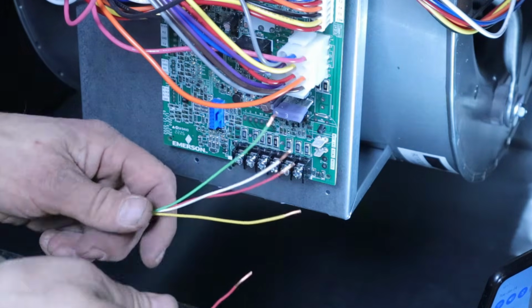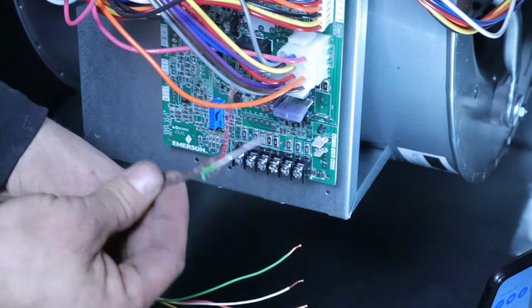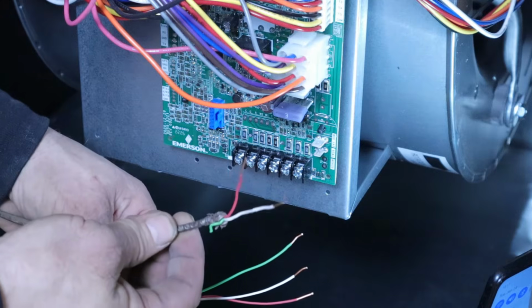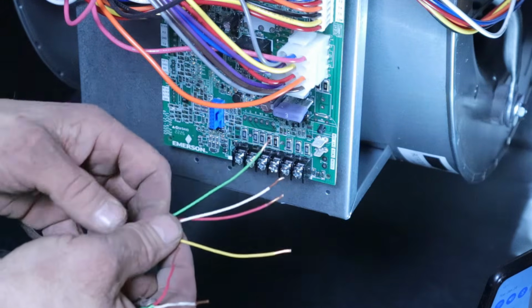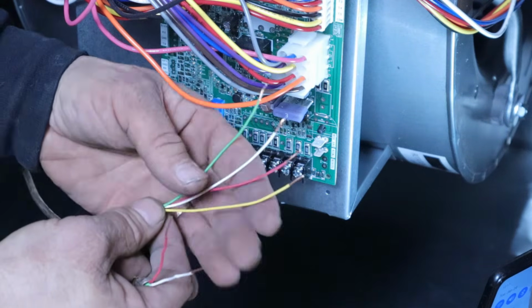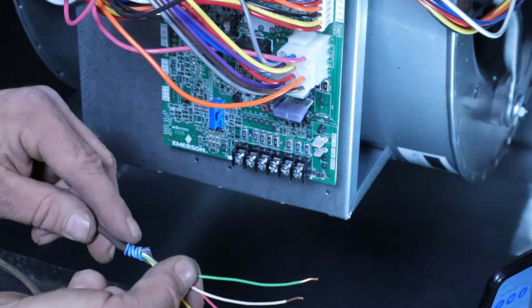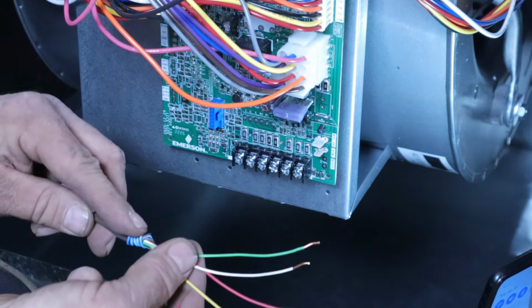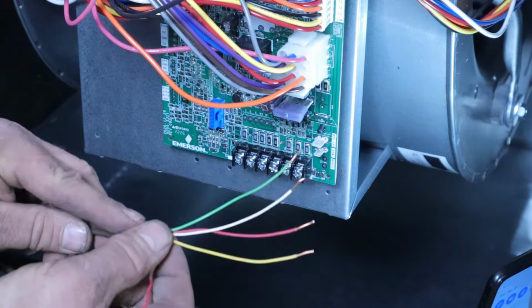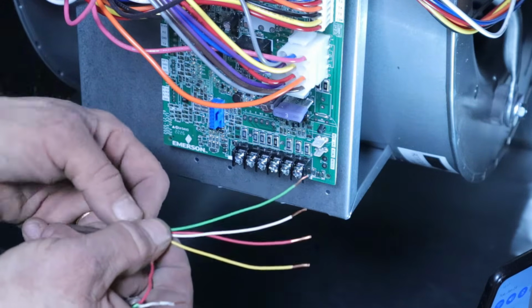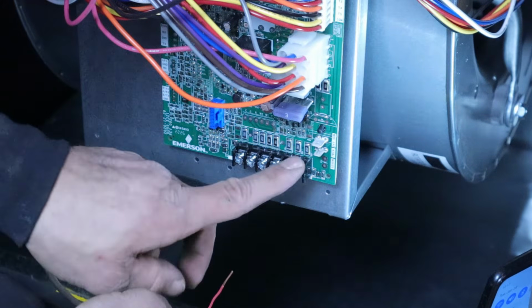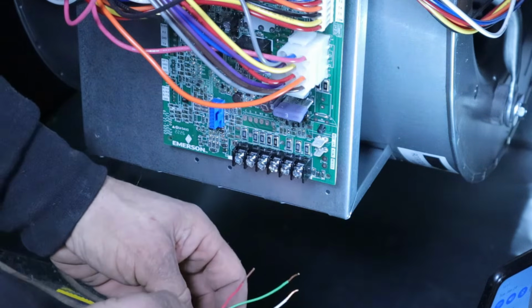Alright, so here we have our two thermostat wires coming in. The red and white is for the condensing unit for the air conditioning. And we have a green, white, red, and yellow that's coming from our thermostat. We also have a blue on here, but you don't need that, even though the customer has a Nest thermostat, that one doesn't need a common wire. So we're wrapping that back. I'm going to start with my cooling.